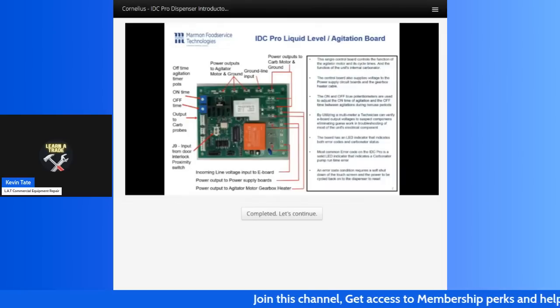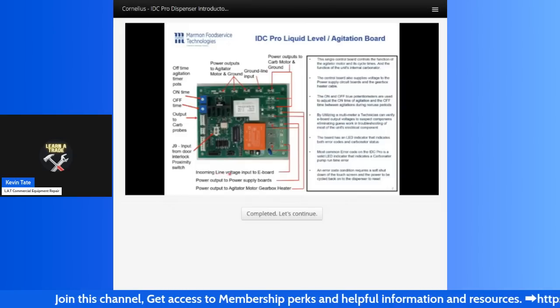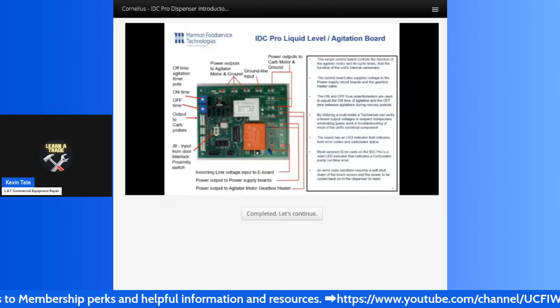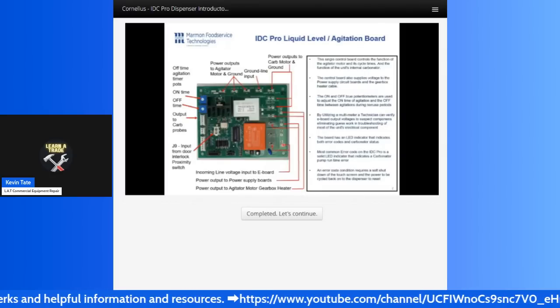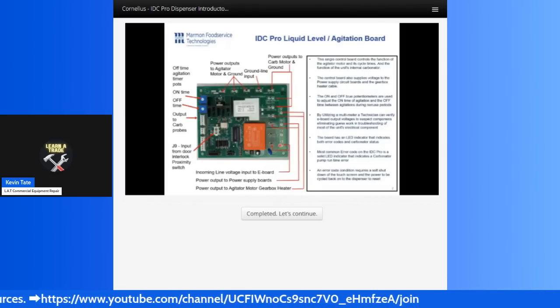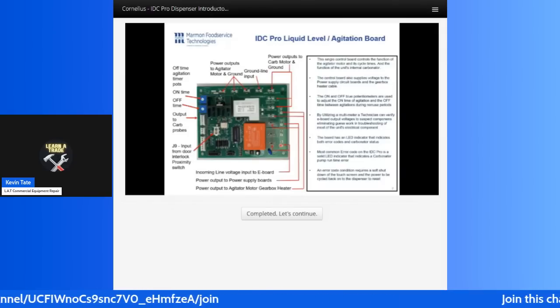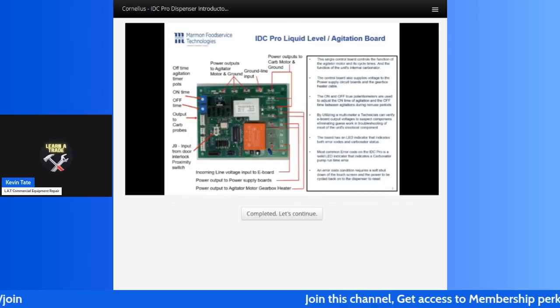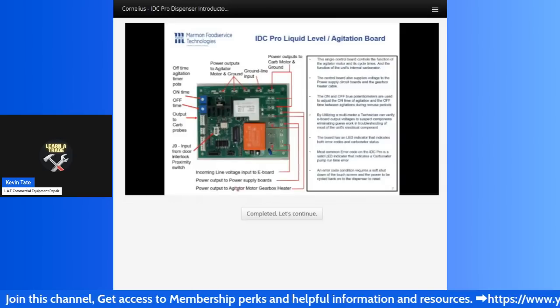Let's go around the board and talk about some of the components on here. First of all, we'll talk about the incoming line voltage to the electrical board itself. These two spade terminals here, that's the main power coming in from the wall outlet through the power cord, the harnessing of the unit, and of course up to the board. So you're going to have your hot and your neutral. And then also that power cord is going to have a ground wire, a green ground wire that is from the outlet that references earth ground. And that goes to this terminal on the board here.